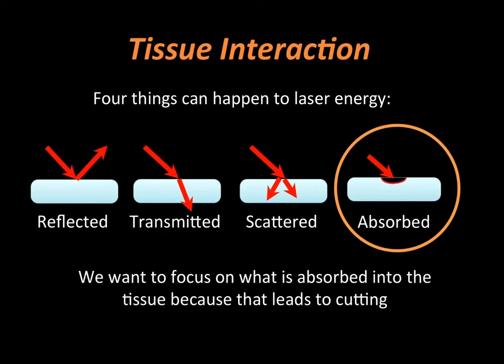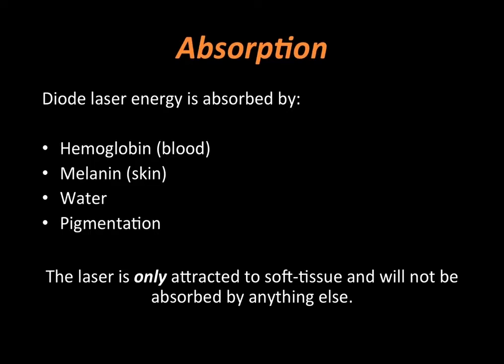which leads to proper cutting. The diode laser energy is absorbed, as you can see, by hemoglobin, melanin, water, or pigmentation. The laser is only attracted to soft tissue and will not be absorbed by anything else. The darker the pigmentation, the more attraction the laser energy will have. This is how a laser works and why it only cuts soft tissue and not bone.